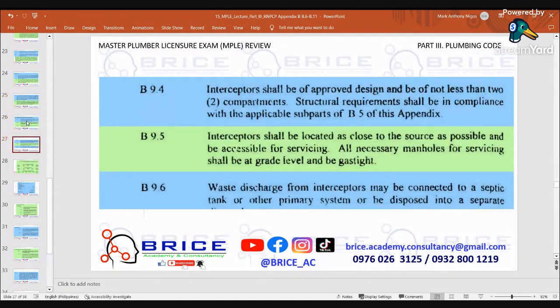Interceptor shall be approved, designed, and be of not less than 2 compartments. Structural requirements shall be in compliance with the applicable subparts of B.5 of this appendix. Interceptor shall be located as close to the source as possible and be accessible for servicing. All necessary manholes for servicing shall be at grade level and be gas tight.